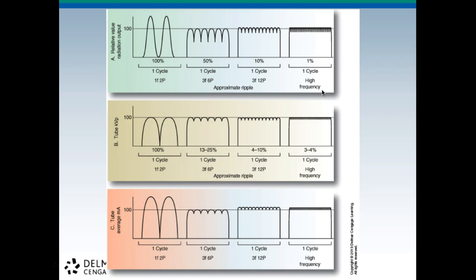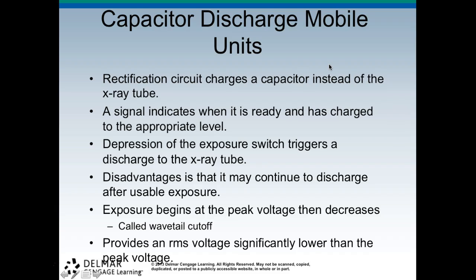So if we look back at this, if we're looking at the tube kVp, we're at 3 to 4% ripple with a high frequency, which is great. And then our amperage here, and we've got our output, so it's 1%. That's great. Okay, capacitor discharge mobile units. So the rectification circuit charges the capacitor instead of the X-ray tube. The signal indicates when it's ready and has a charge to the appropriate levels.